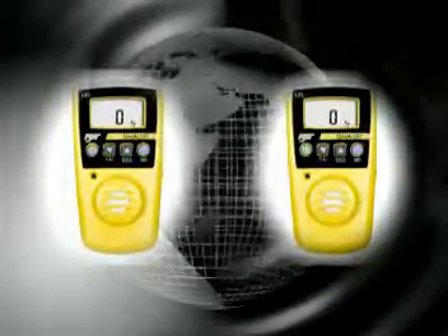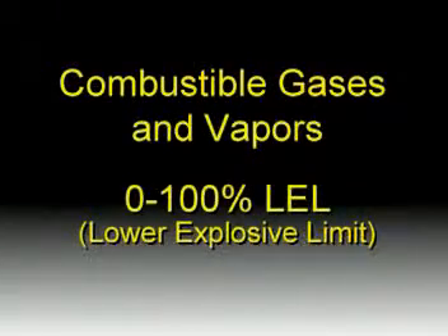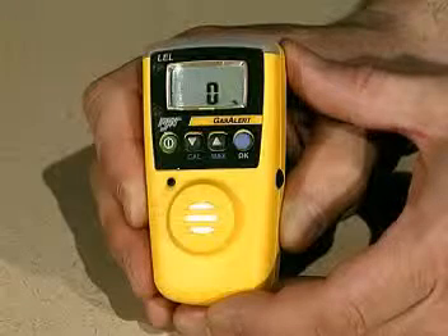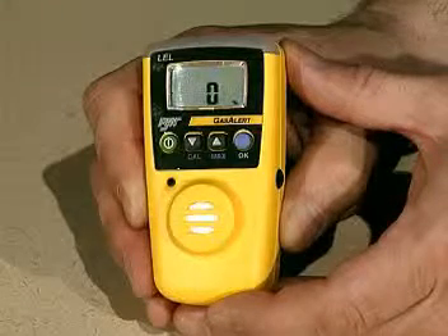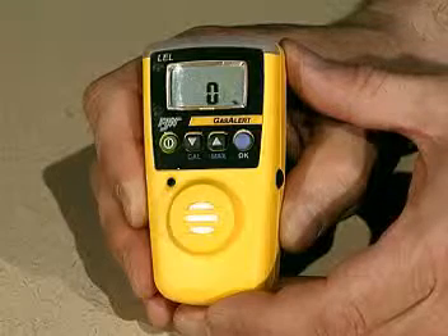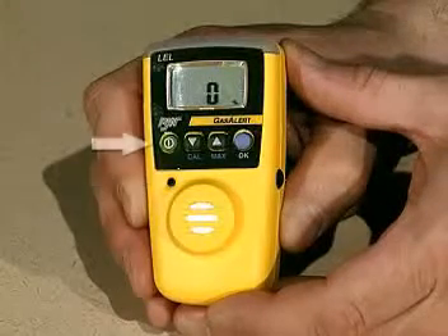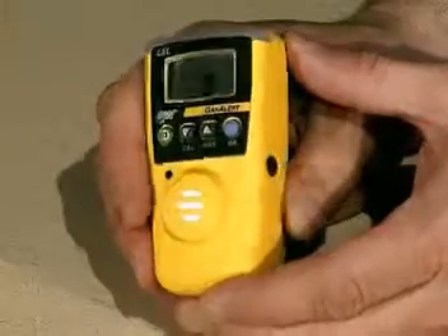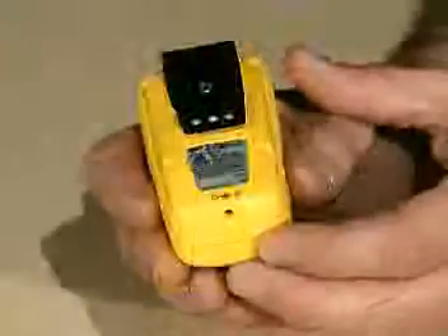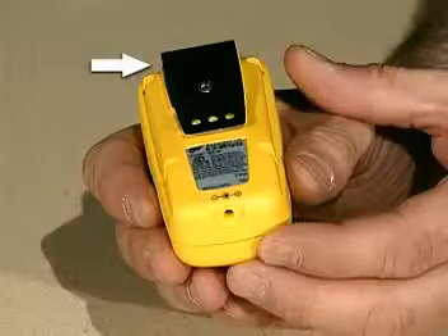An optional model for high noise areas is available with an internal vibrating alarm that pulses in sync with the audible visual alarms. The GasAlert-LEL monitors the atmosphere continuously for combustible gases and vapors in the 0 to 100% LEL, or lower explosive limit. Features include a rugged safety yellow enclosure, wide-angled visual alarm bar, large status at a glance alphanumeric display, audible alarm, one-button on-off operation, alarm port that accepts an earphone, charging port, and a high-tension belt clip.